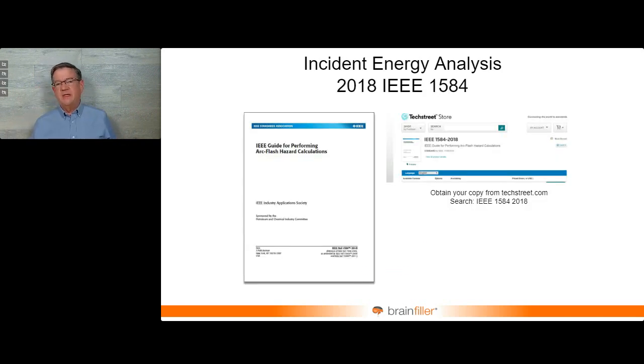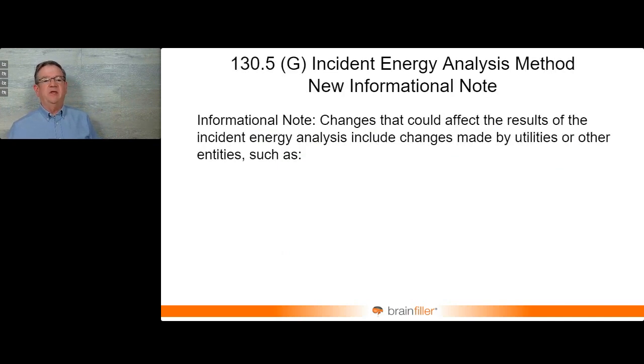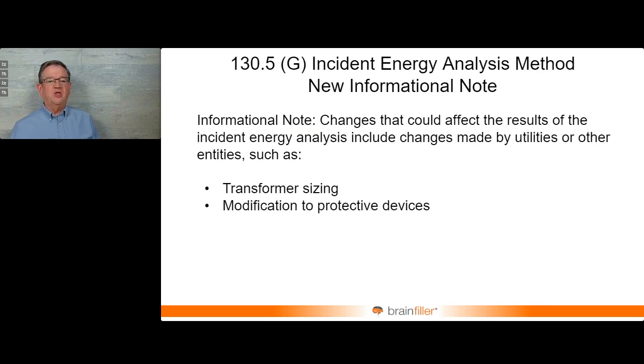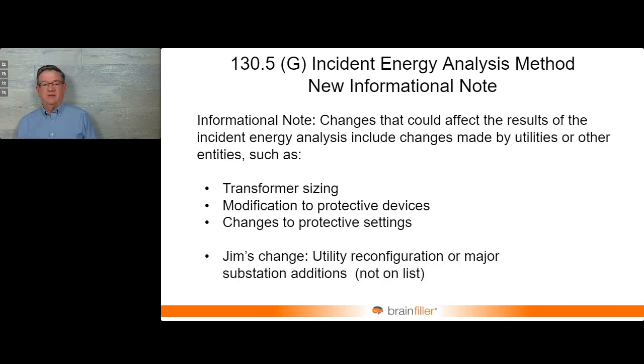The incident energy analysis is conducted based on equations from IEEE 1584. A lot of software will calculate all this for you. And the changes that 70E references: change in the transformer, modification of protective devices, changes to protective settings. And then one that I added, this one actually is not in NFPA 70E: utility reconfiguration or major substation additions. I added this one because in a past life, this goes all the way back to the 1980s, I was in charge of the transmission short circuit studies group for a really large utility. And I could see what happens firsthand.